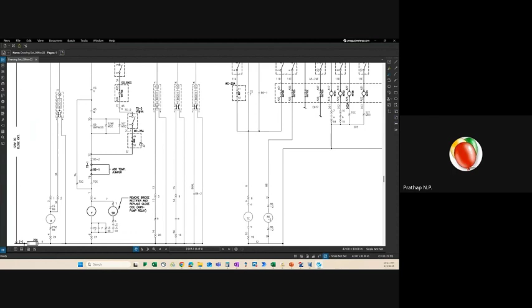It should probably be OUT106, I'm not sure. In this case, it's called a virtual bit or a remote bit, depending on the protocol you use. You would put a remote bit or a virtual bit in that equation, in that contact OUT106. So whenever the utility wants that generator to connect, they will send a close command from their control station somewhere few kilometers down. We don't know where that control station would be, but they will send that information and they would close this contact.